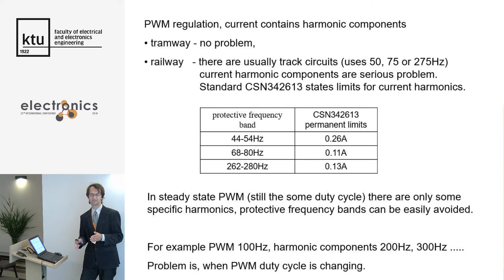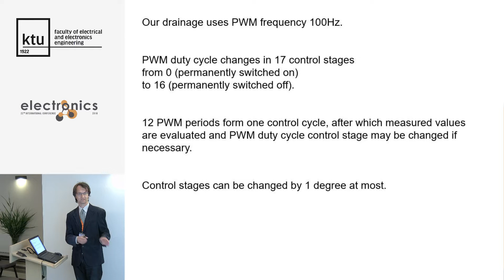In steady state, when PWM has the same duty cycle and so on, there is no problem, because we have, for example, 100 Hz switching frequency, and harmonic components are at 200 Hz, 300 Hz, and so on. But the problem is when PWM duty cycle is changing. We use this 100 Hz frequency, and we change duty cycle in 17 control stages from 0 to 16. The control stage can be changed step by step only by 1 degree at most.